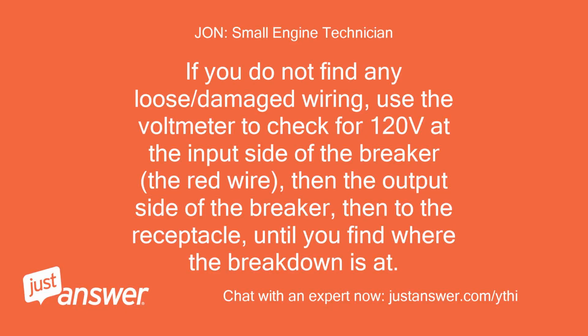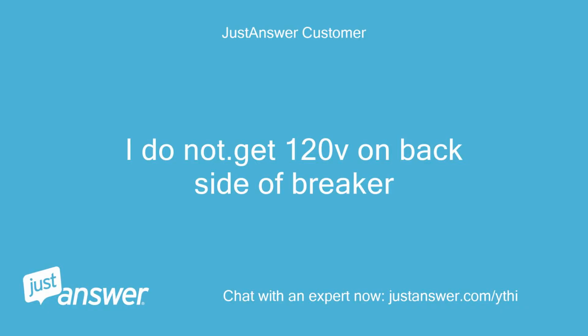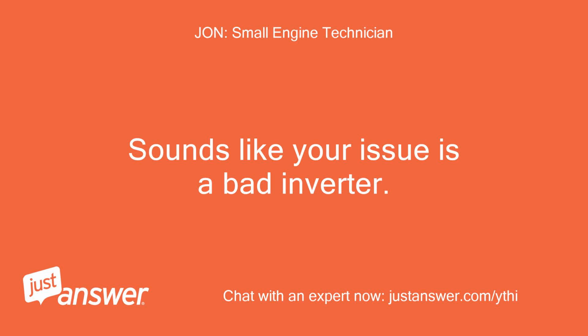If you do not find any loose/damaged wiring, use the voltmeter to check for 120 volts at the input side of the breaker, the red wire, then the output side of the breaker, then to the receptacle, until you find where the breakdown is at. I do not get 120V on back side of breaker. Sounds like your issue is a bad inverter.